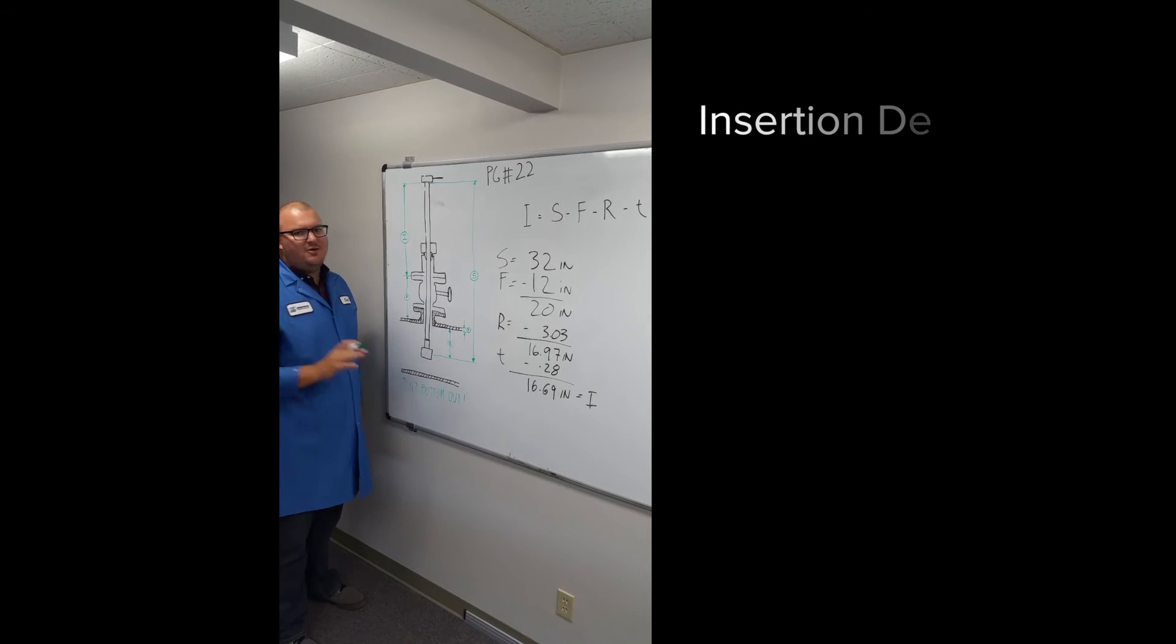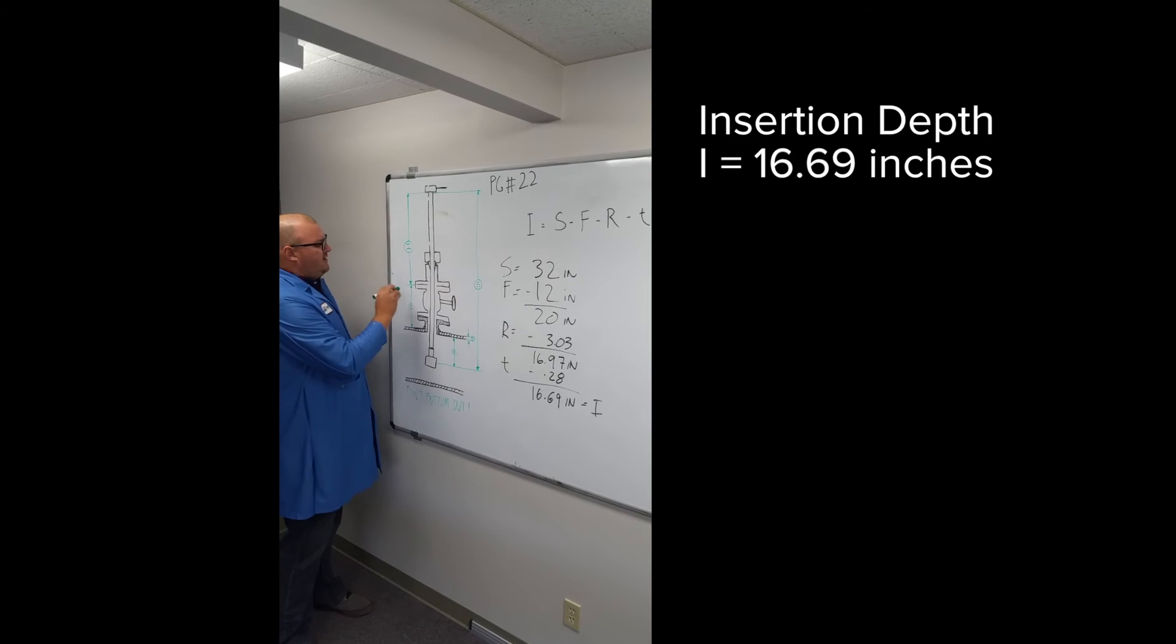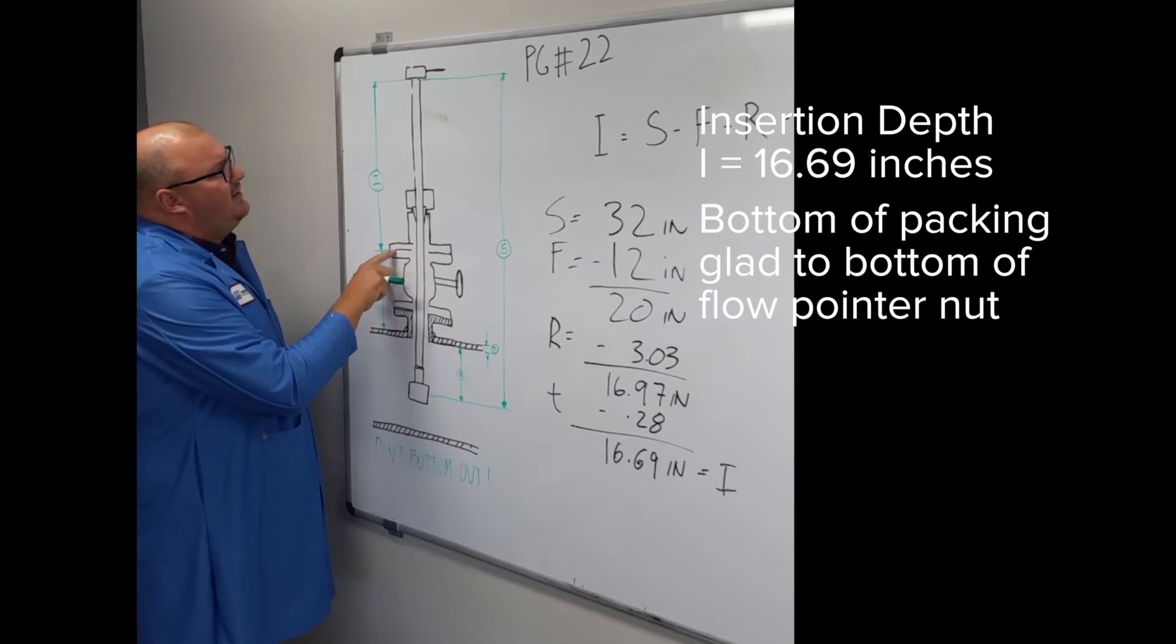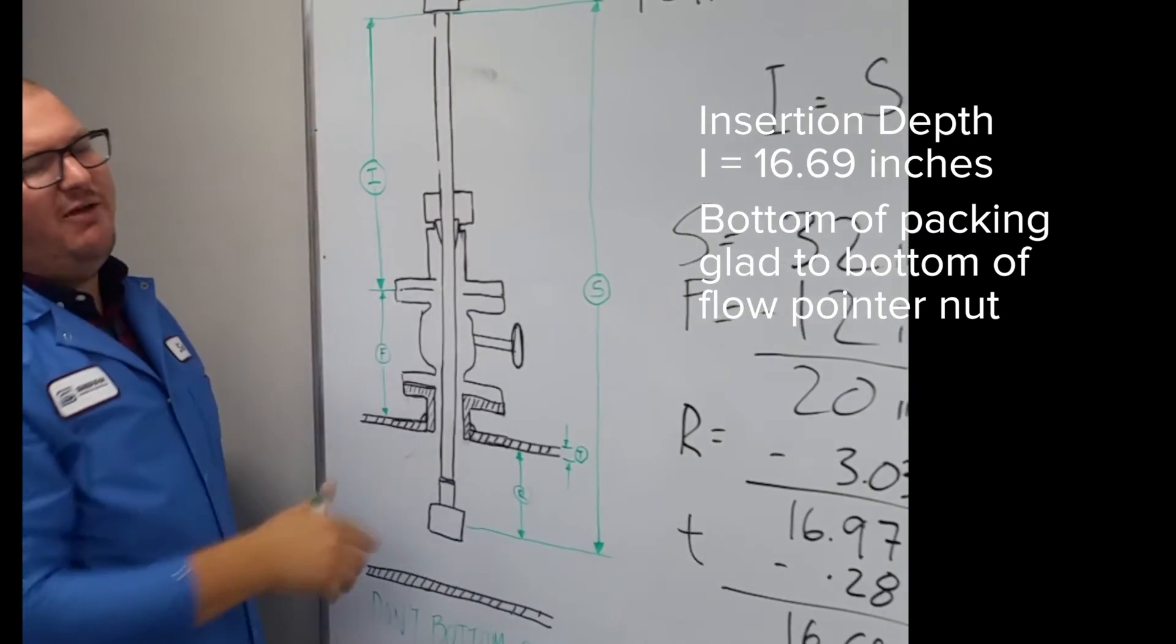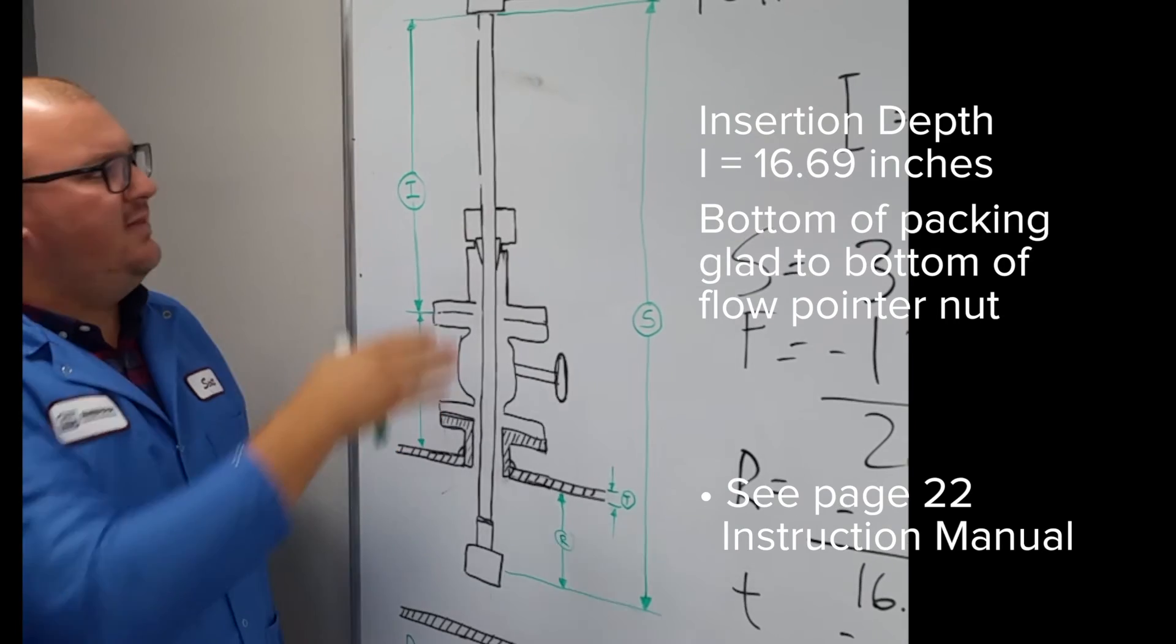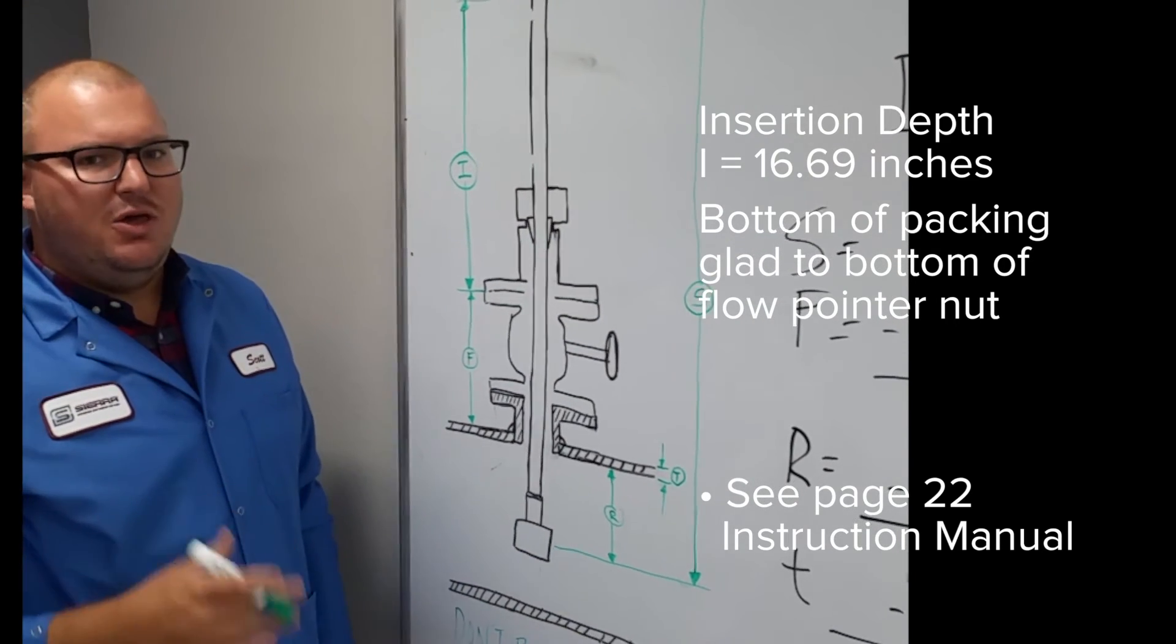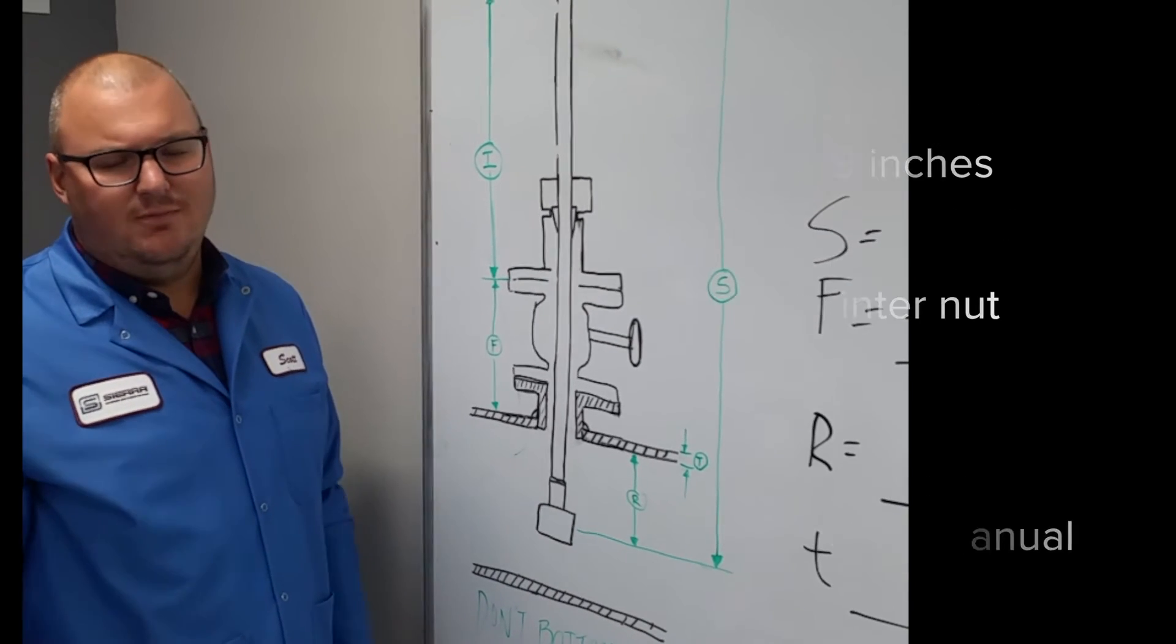We've calculated our insertion depth, 16.69 inches. And that insertion depth is going to represent the bottom of our packing gland to the bottom of the pointer nut. And you can reference page 22 in the manual to see this kind of diagram that I've drawn right here. But now, let me show you how to mark the retractor with this insertion depth and then get the probe to where it needs to be.